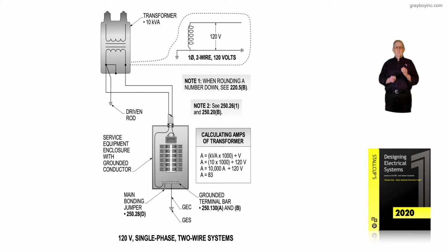Now, in closing out this illustration, let's review Note 1. When rounding a number down, we see 220.5(B). And when we say rounding a number down, we're talking about if you had, say, 83.5 amps, that could round up to 84 amps. If you had 83.4, you'd round down to 83 amps. However, Article 240 would allow the user to take the ampacity of the conductor. In fact, it's 240.4(B) as in boy.